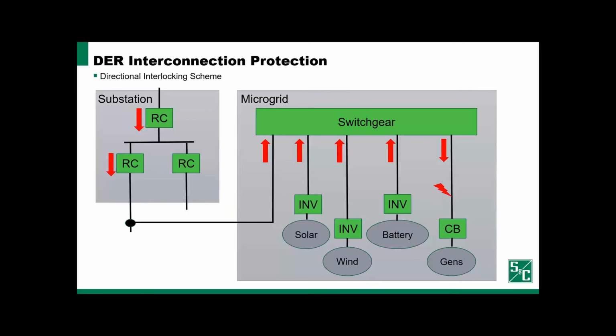This figure, again, is a great way to show an example of how exactly this would work. Let's consider an example fault over on the far right by the generators here. In this situation, we'll see current coming out of the switchgear on this far right, through this far right circuit breaker. And the relay associated with this device can send a blocking signal to each of its neighbors here so that they restrain operation and allow the device closest to the fault to operate first. Similarly, the switchgear breaker and its associated relay can send a GOOSE message up, blocking its first upstream device, which is at the substation, and telling it to hold off until downstream protection operates, and so on. And this scheme can result in the correct device operating very quickly while maintaining selectivity and ensuring the correct device is operating.